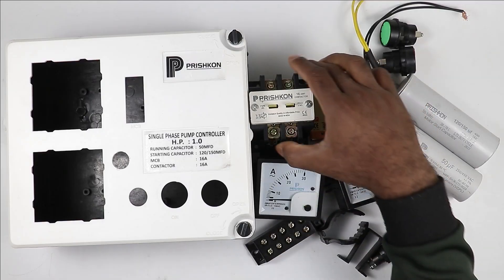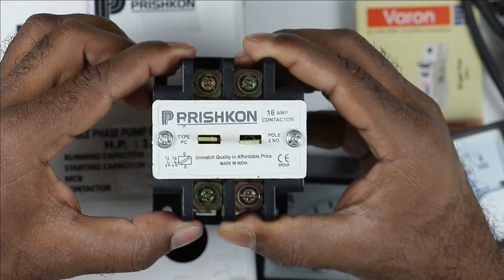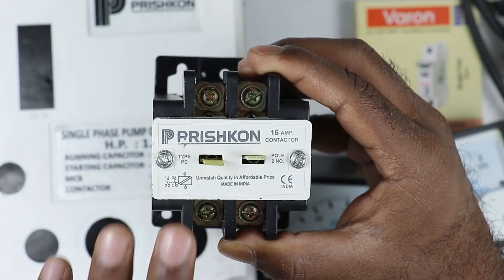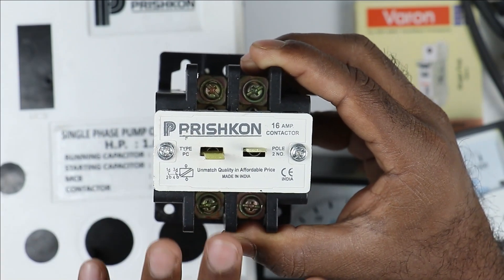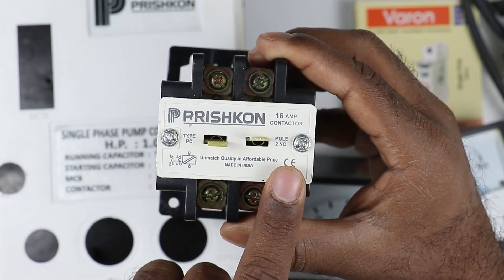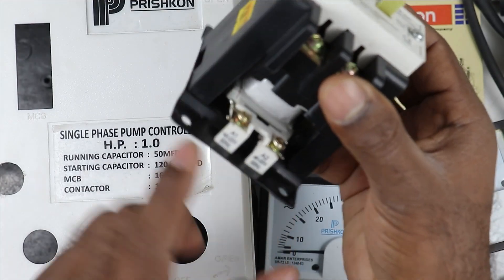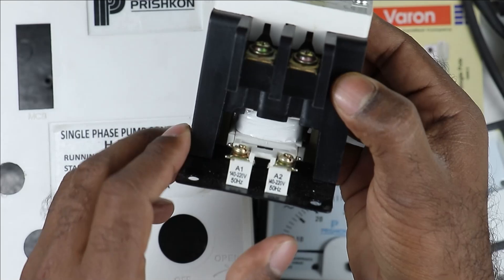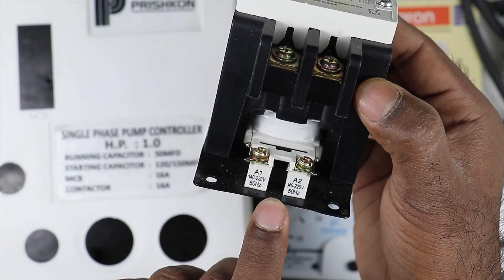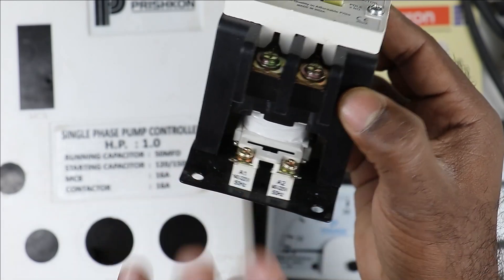Apart from the capacitors, we have to use a contactor. I am using a two pole contactor with a current rating of 16 ampere, meaning we can flow a maximum of 16 ampere through its power wiring. We also need to pay attention to the coil voltage — this contactor's coil is rated 40 to 220 volt, so we can provide single phase power supply to operate it.